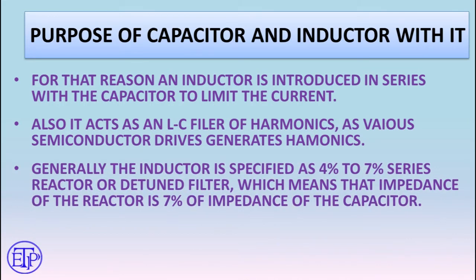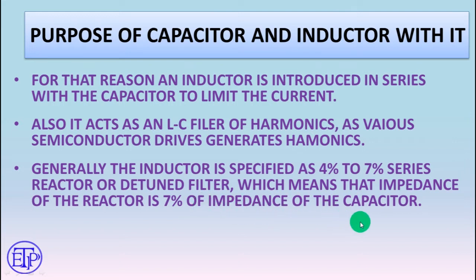We will see how the inductor is specified. The inductor is specified as a 4% to 7% series reactor, or detuned filter. Whenever you specify a capacitor bank with an inductor, you write that we need such-and-such amount of KVAR with a 7% or 4% inductor. This means the impedance of the reactor is 7% of the impedance of the capacitor.